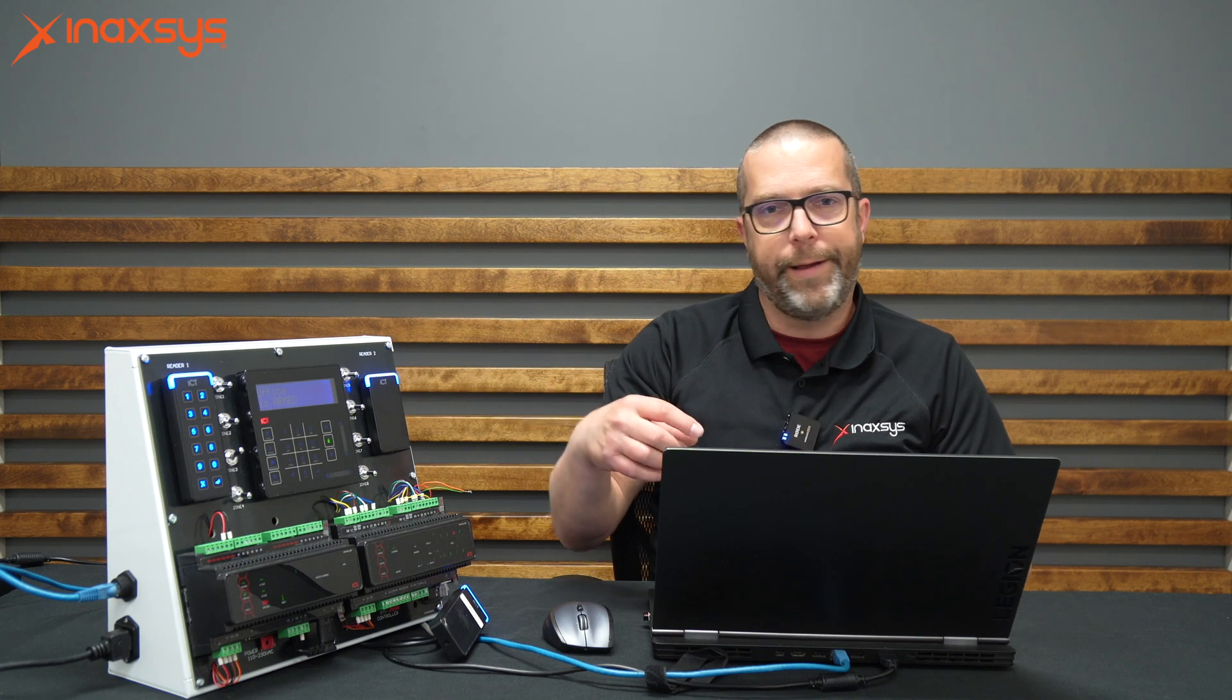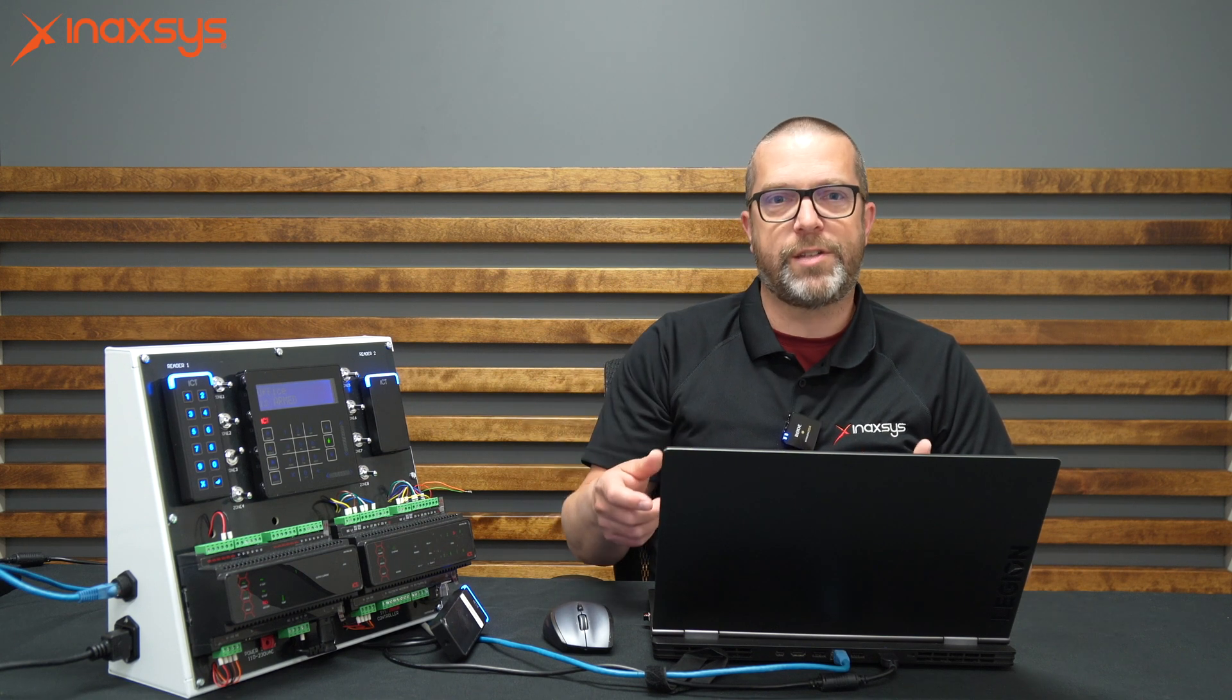If you follow these simple steps, you won't have to call tech support. You disarm everything, make the programming changes, save so the download triggers the changes to the panel. Then you may have to do a module update if you change zone options like removing resistors or changing the resistor setting. After this is completed, you can arm the partition or area and test.